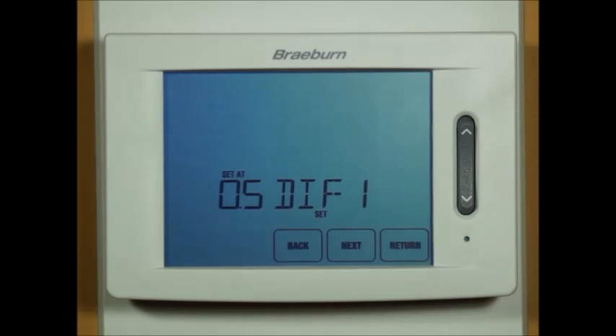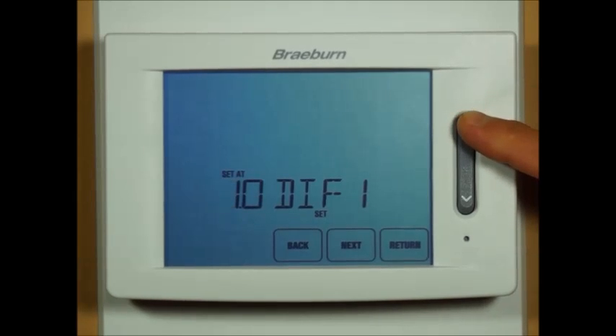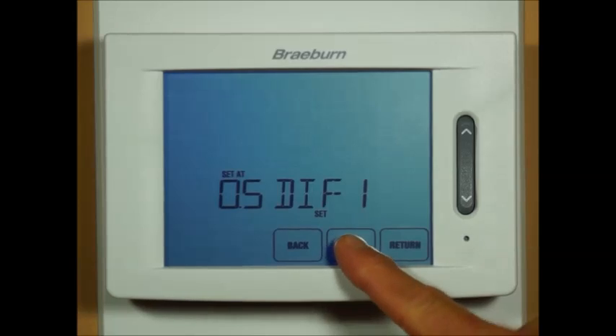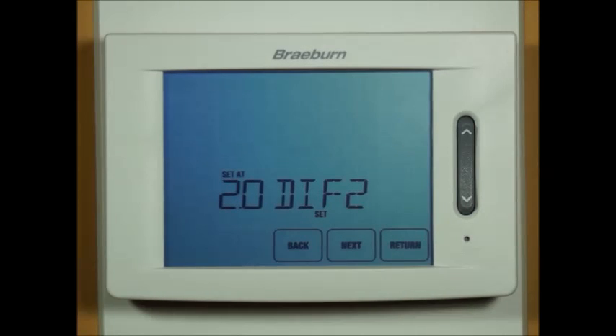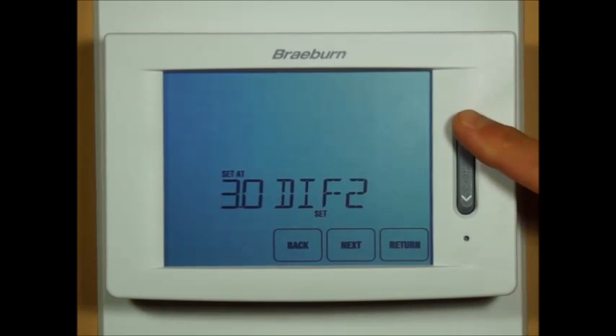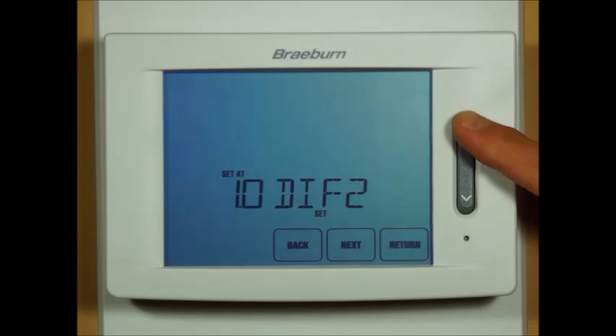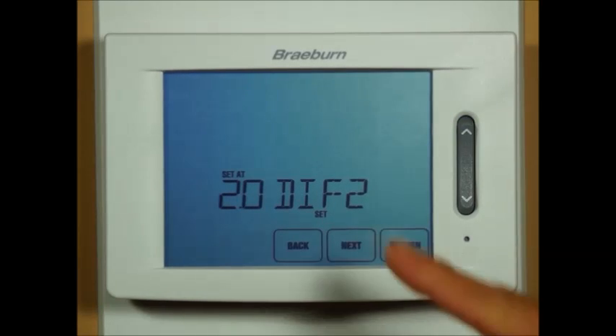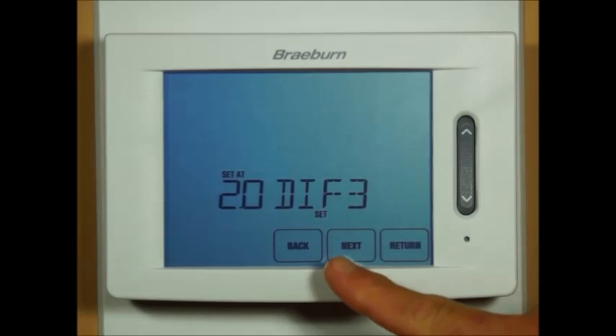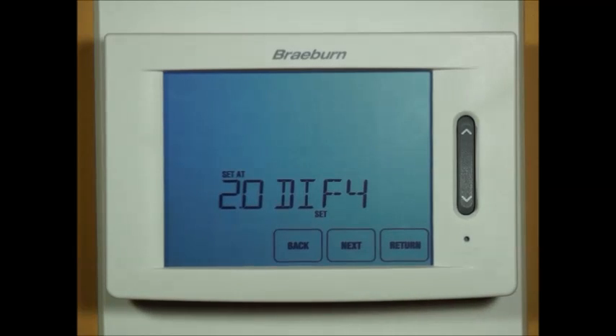Your first stage temperature differential defaults at 0.5 degrees; you can select one degree or two degrees. Your second stage differential defaults at two degrees; you can select three, four, five, six, one degree, or the default two. Your third and fourth stage temperature differentials have the same setting options as your second stage differential.